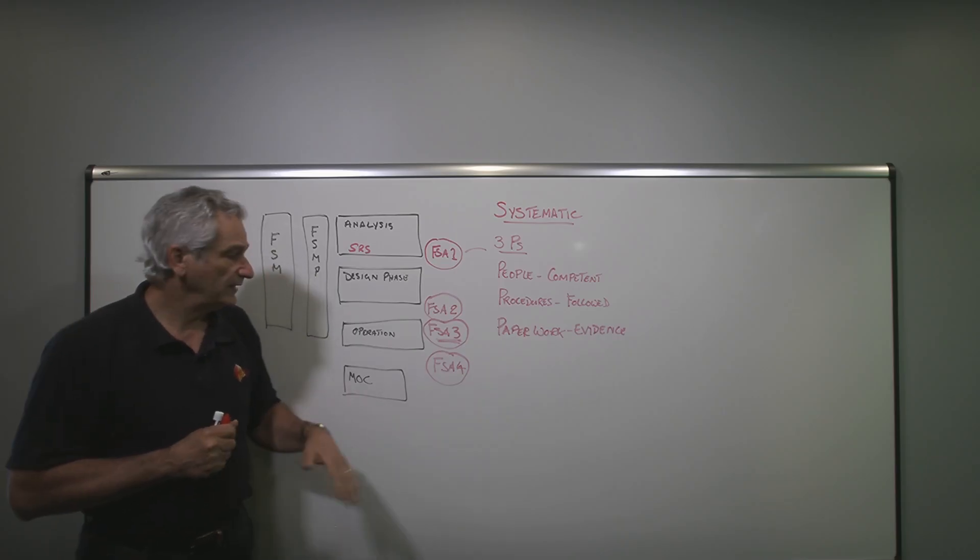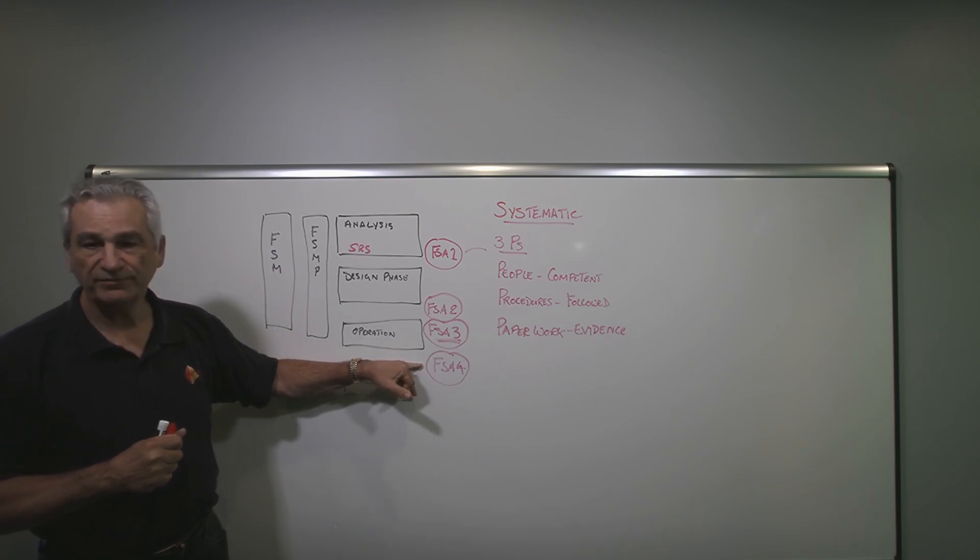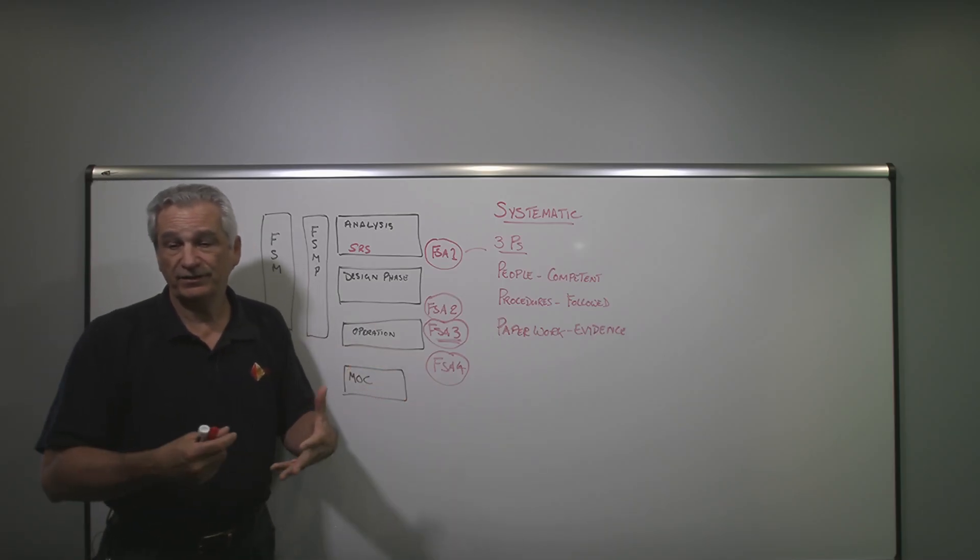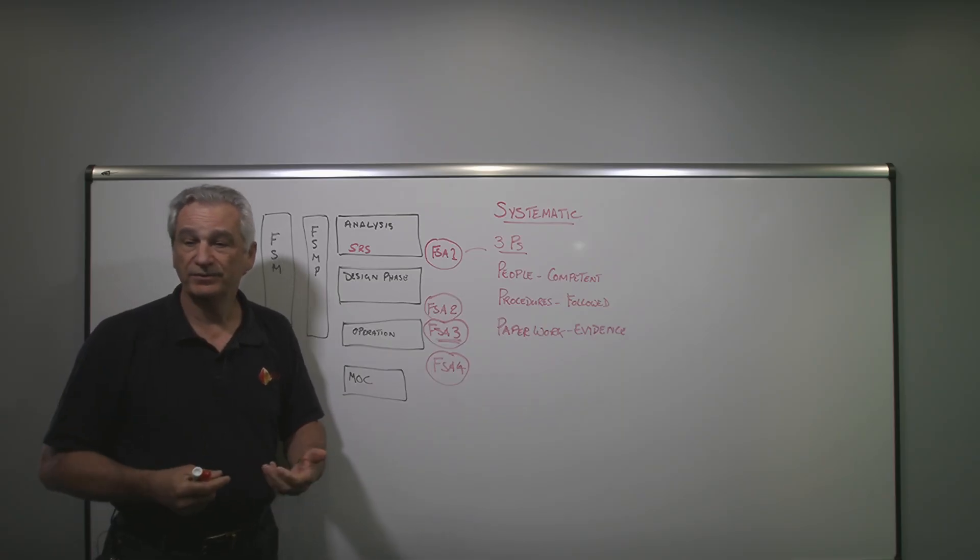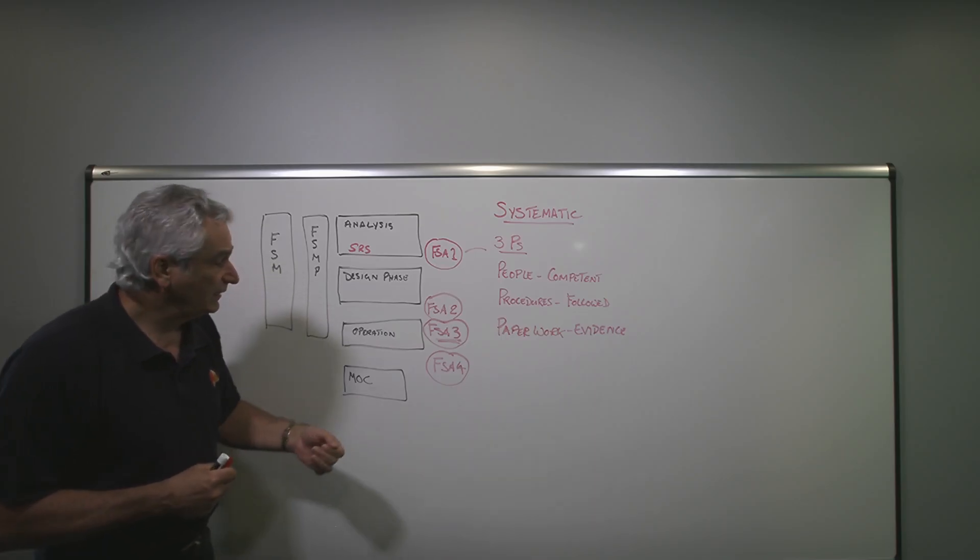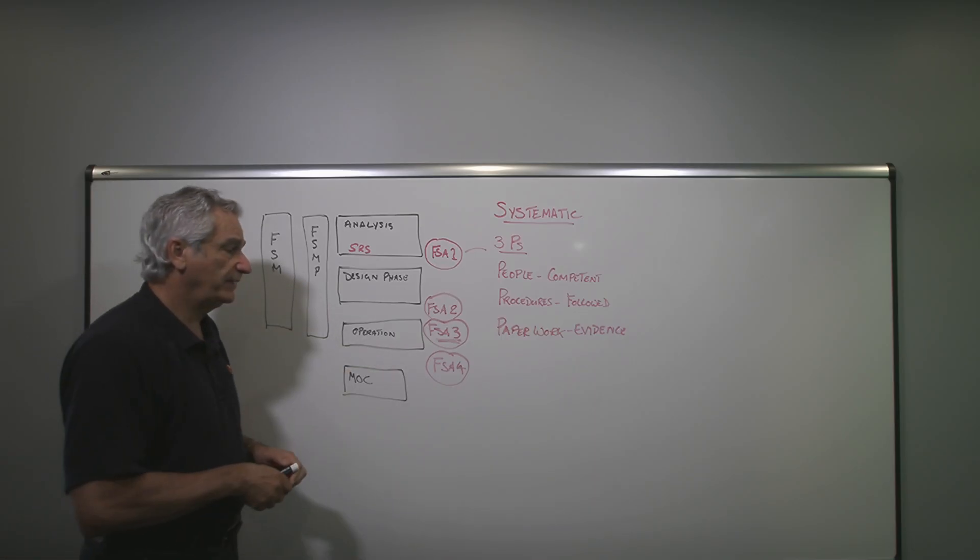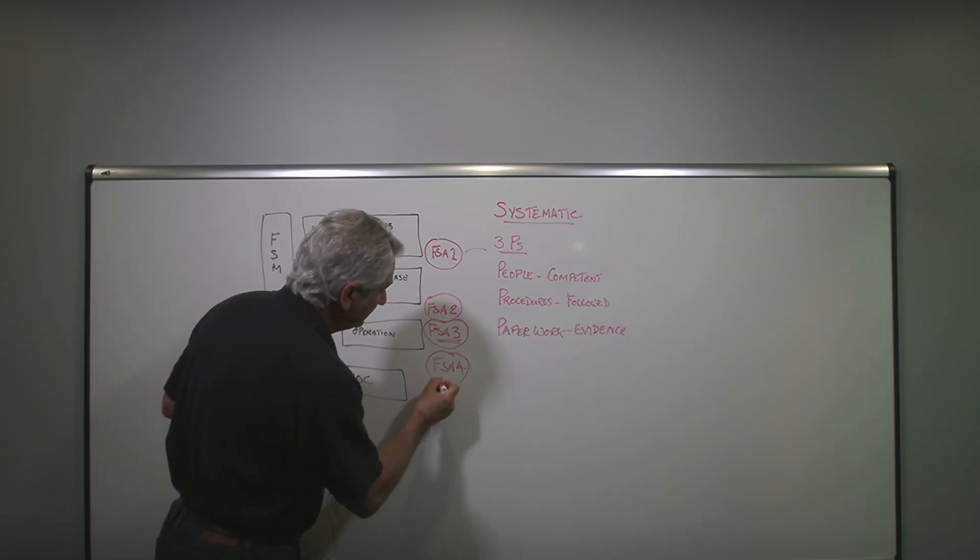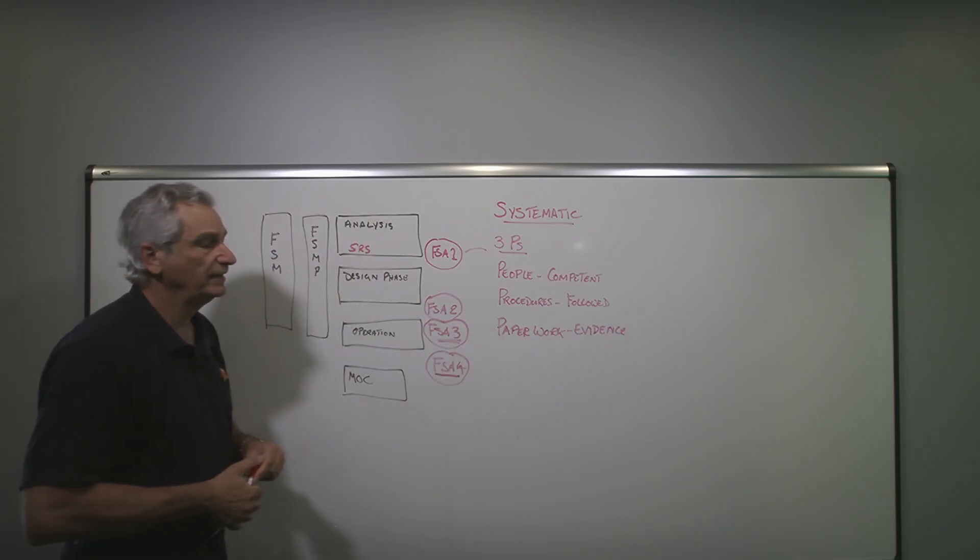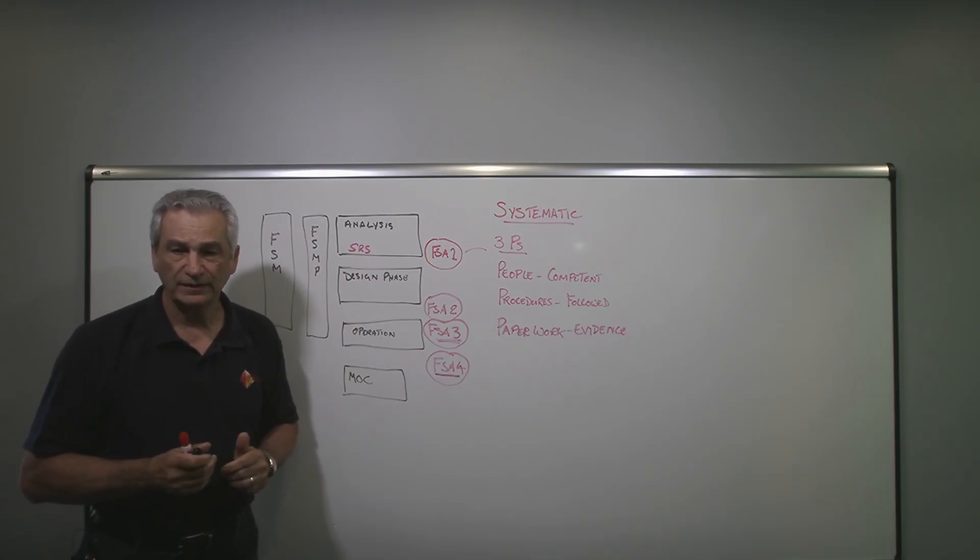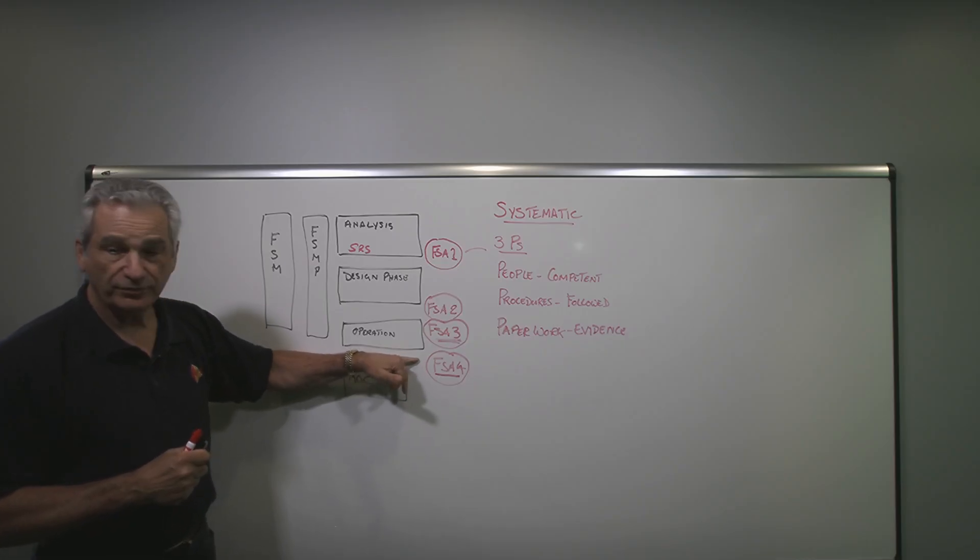Whereas with a performance standard, it still says this is what you need to do, but it doesn't tell you how to do it. All it says is that you can do it any way you want, as long as you can prove you're meeting your original design requirements and your targets. In other words, we have to be able to compare to key performance indicators. Because it's a performance-based standard. If we're not looking at our performance, how do we know that we're still maintaining our original design targets? So the FSA-4 is another mandatory requirement. And again, the standard doesn't tell you how often to do it. It says it needs to be done after some period of time in operation.